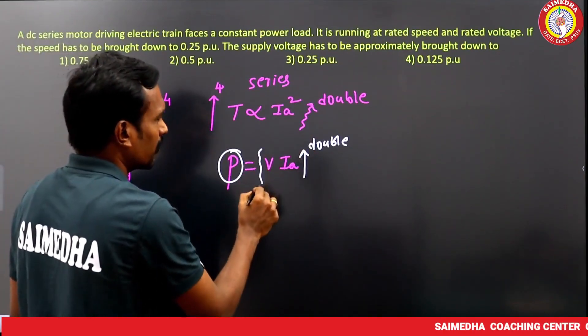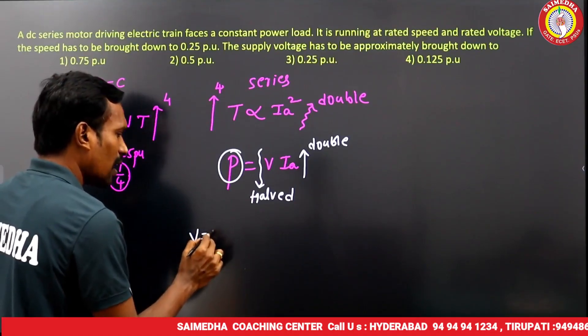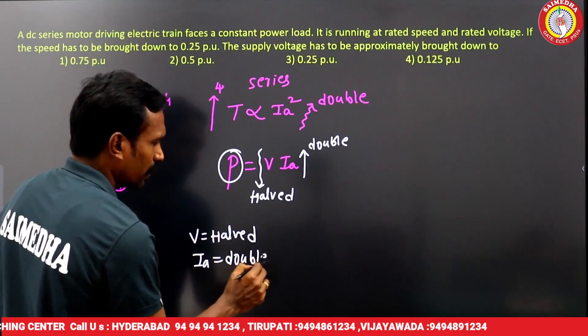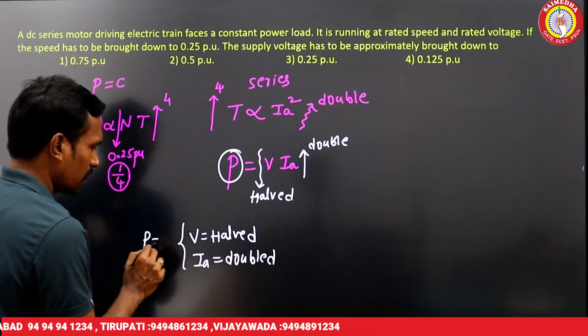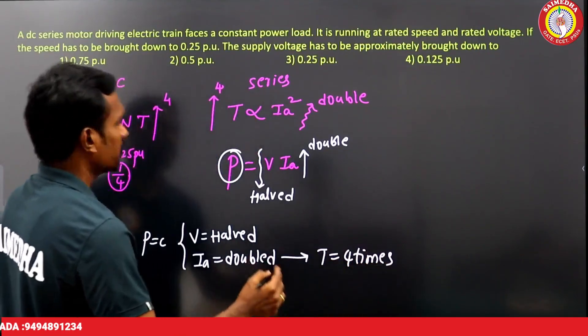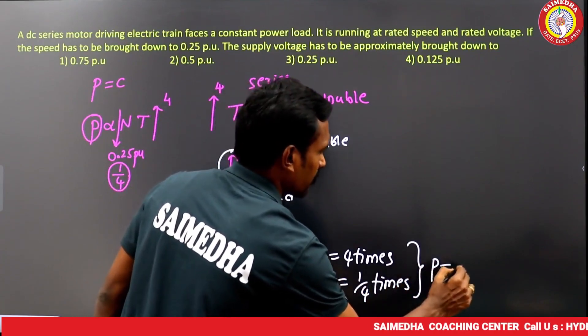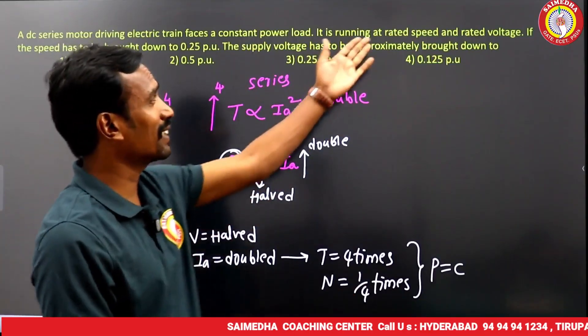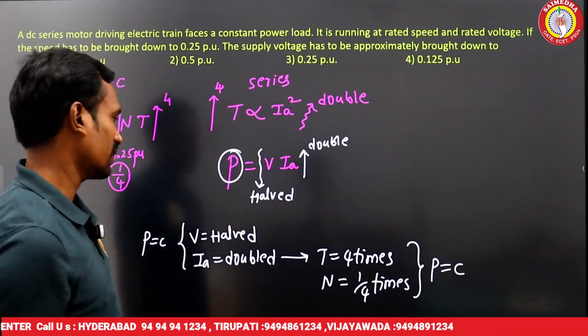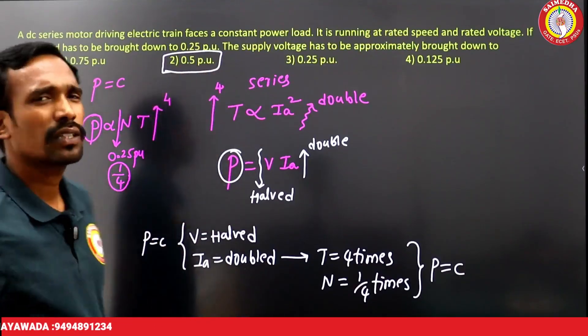When voltage is halved and current is doubled, power remains constant. With current doubled, torque increases by 4 times. With torque 4 times and speed reduced to 1/4, power is again constant. Therefore, the supply voltage must be reduced to 0.5 per unit.